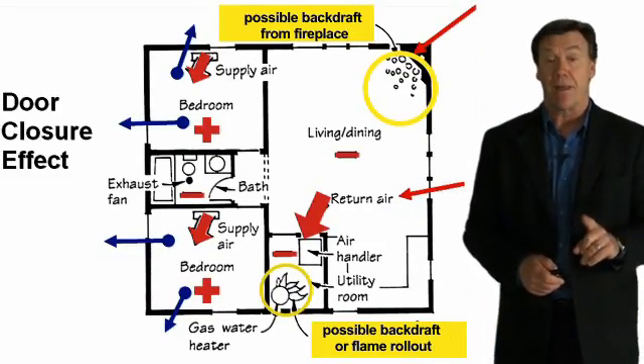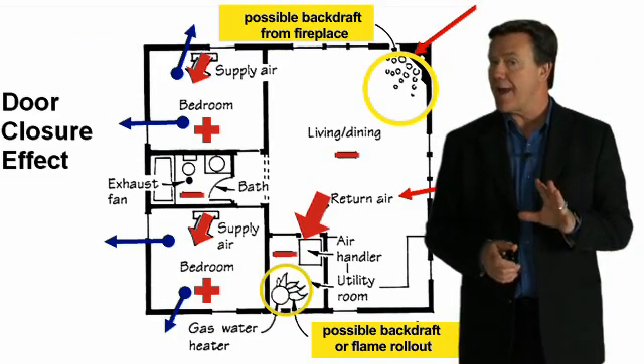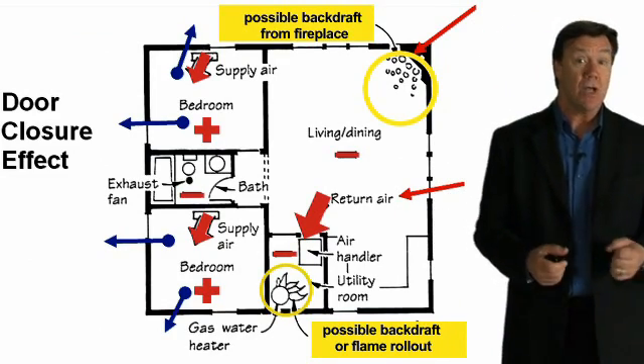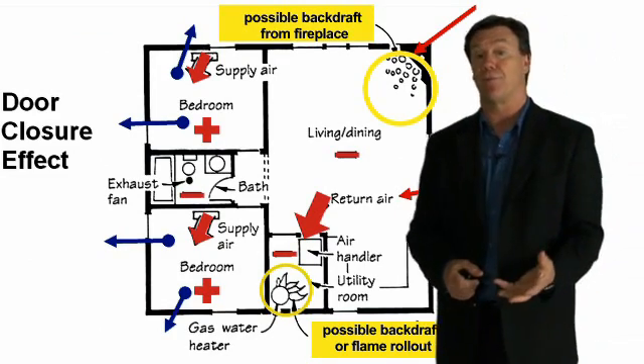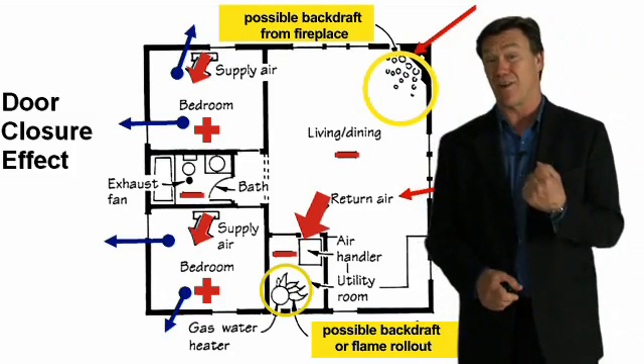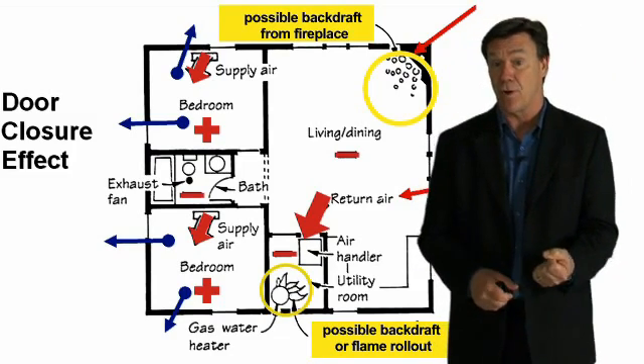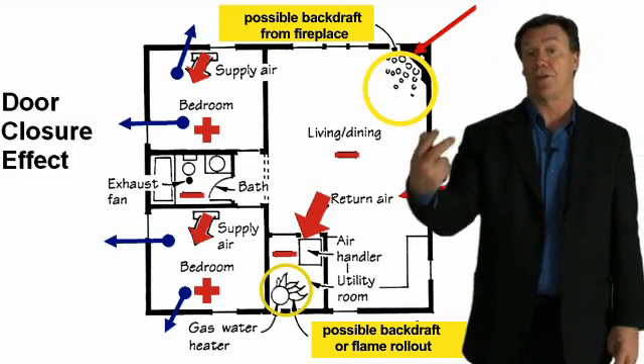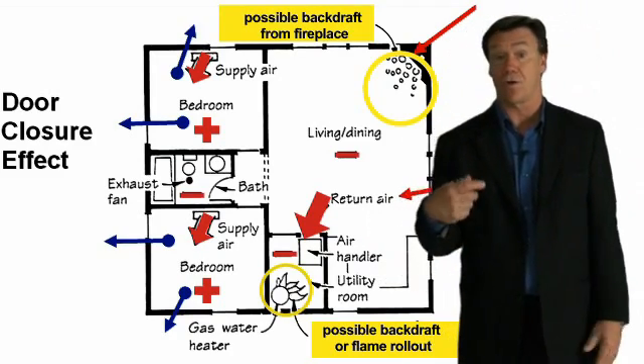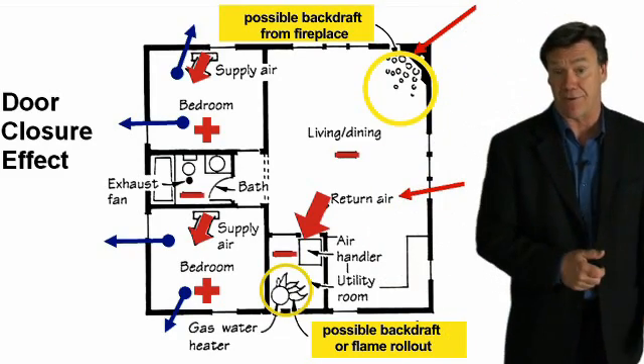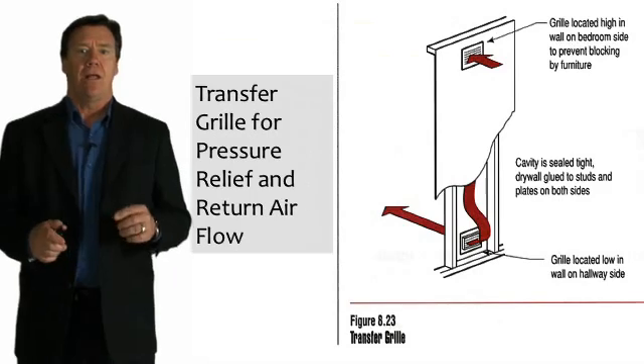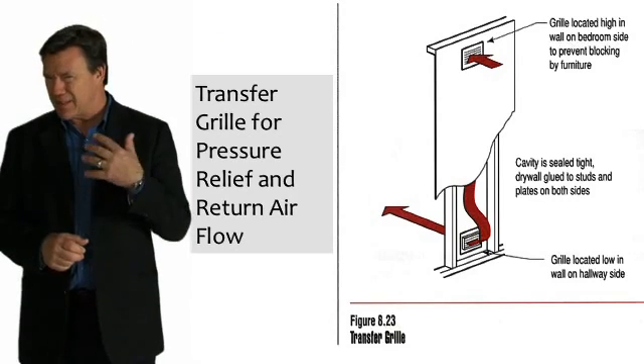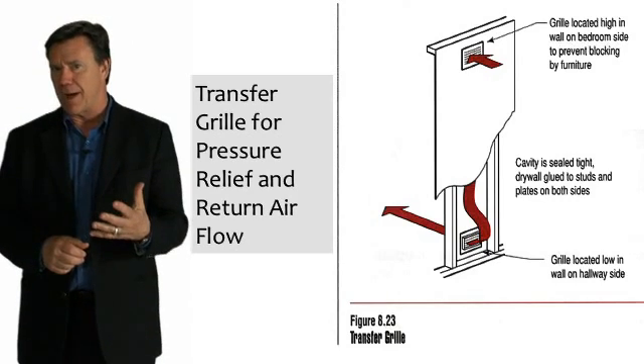However, many homes today do not have return air ducts in each room — they might have one central return. So if we have a bedroom door closed, that could cause that room to be under a positive pressure, which might cause an adjacent room to be under negative pressure, which could cause a fireplace to backdraft. When bedroom doors are closed, they can, as mentioned, be under a positive pressure.